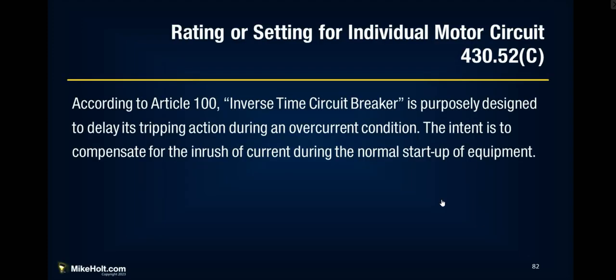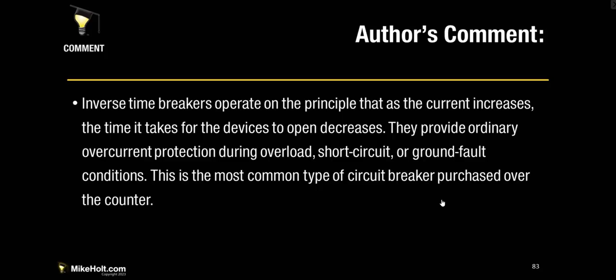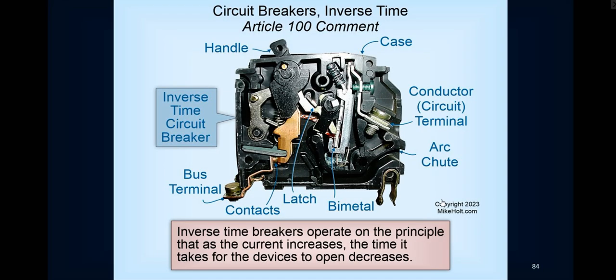I'll say that. According to Article 100, an inverse time circuit breaker is purposely designed to delay its tripping action during an overcurrent condition, and the intent is to compensate for the inrush current during the normal startup. Inverse time circuit breakers operate on the principle that as the current increases, the time it takes for the device to open decreases, and they provide ordinary overcurrent protection during overload, short circuit, or ground fault conditions. This is the most common type of circuit breaker purchased over the counter.